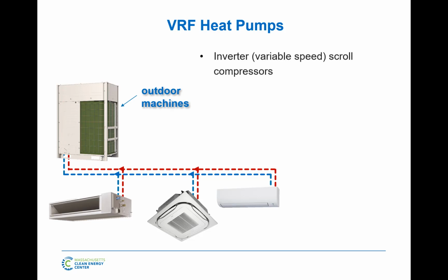This is where you have the inverter, variable speed scroll compressors. So the majority of VRF in North America, we call them 3-phase power and above, the main commercial version of the units, use scroll compressors, and they're all variable speed compressors. These are not digital scroll compressors. Anybody in the industry that knows what those are, digital scrolls are very different. Digital scrolls actually split the plates apart to get part load capacity. An inverter compressor means there is a VFD on the compressor. So it'll actually slow down the compressor at part load and speed it back up.